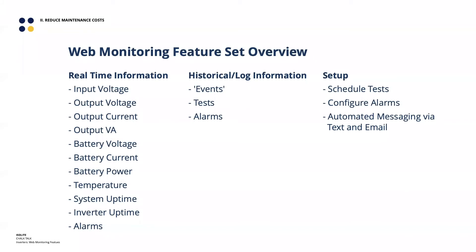Beyond real-time data, the historical information is where this really becomes powerful. Events — anything someone might need to know about, including its duration and start and end conditions — include things like power outages, scheduled tests, and any active alarms. All of that can be viewed with start and end times to see exactly what's happened throughout the entire history of the device. You can also schedule tests, configure alarm thresholds, and configure who gets automated text message and email alerts — all through the web monitoring portal.